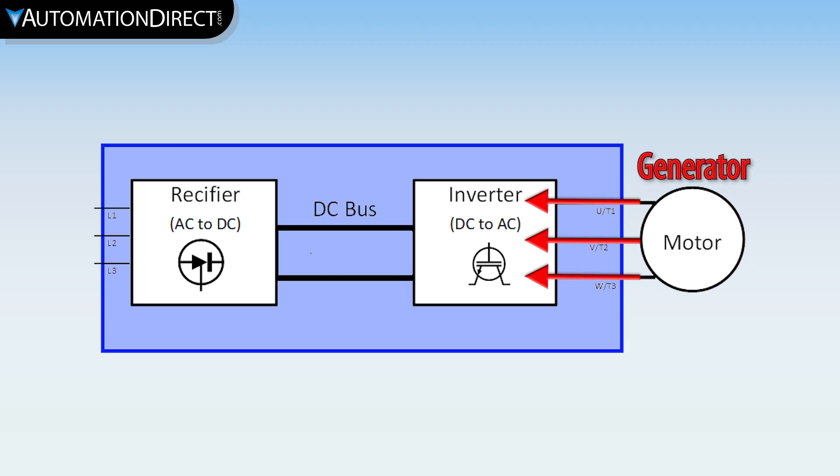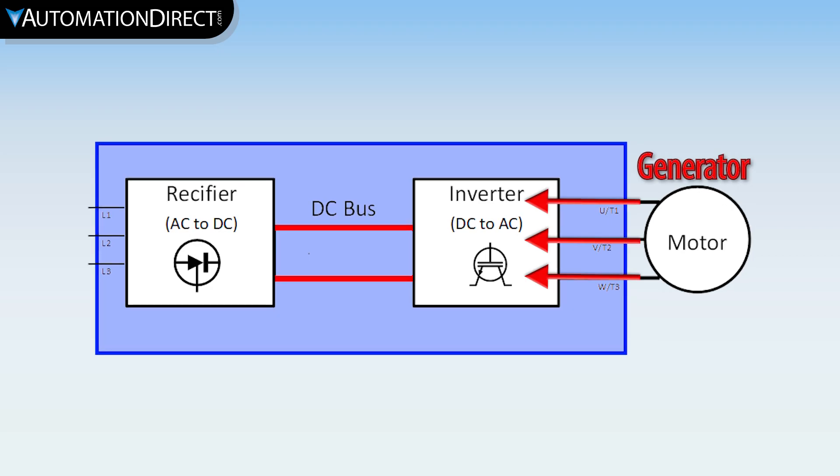But on an AC or DC drive, this regenerative voltage often has nowhere to go, so it raises the bus voltage and can create an over-voltage fault on the drive, which allows the motor to coast to stop and protects the drive.